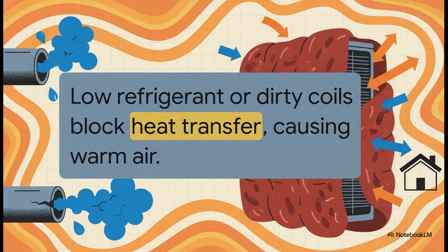Then, of course, there's the classic summer nightmare. Your AC starts blowing warm air. When this happens, it's rarely a big mystery. Think about it. Air conditioning is really just the science of moving heat from inside your house to outside. So if it's blowing warm, your system has simply lost its ability to transfer that heat. And that almost always comes down to one of two things: either low refrigerant escaping from a leak, or dirty coils acting like a thick blanket and physically blocking the heat transfer from happening.